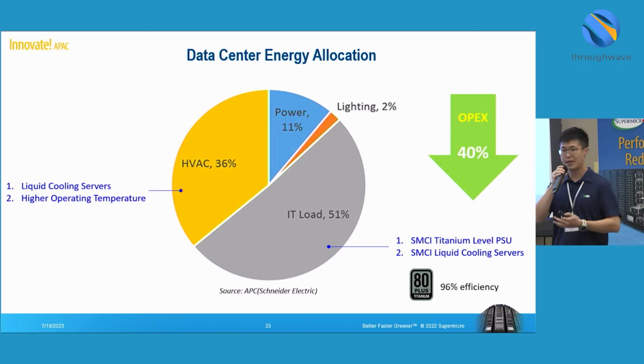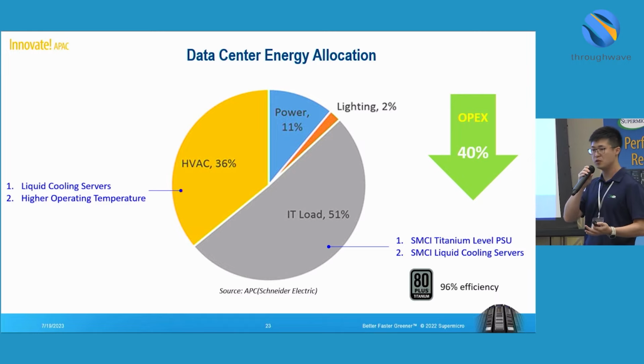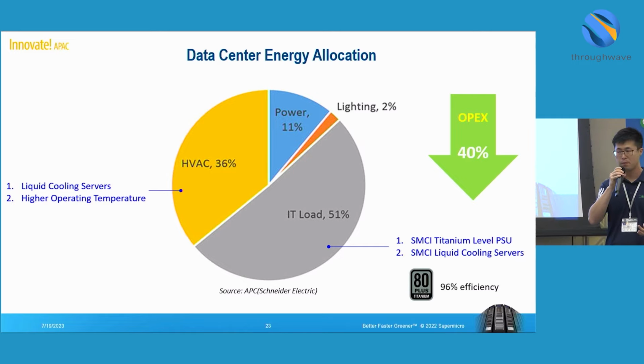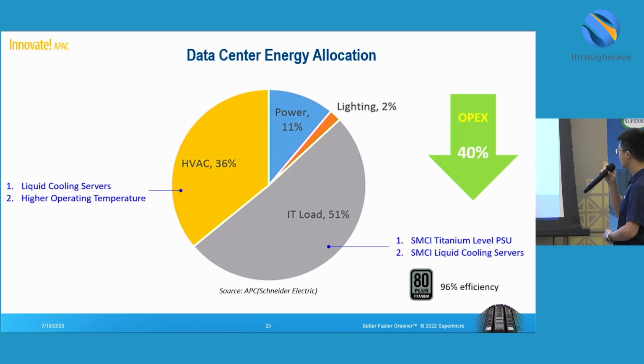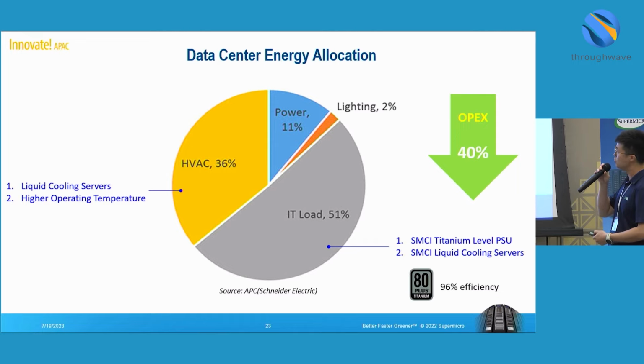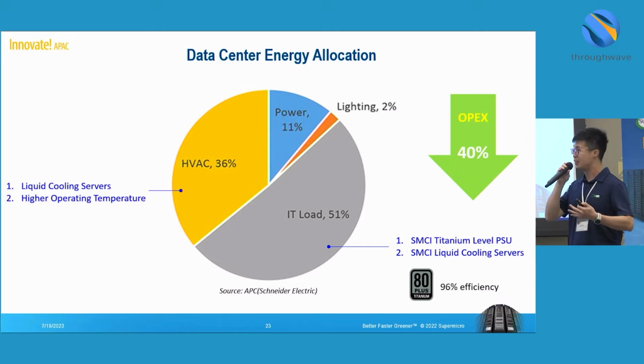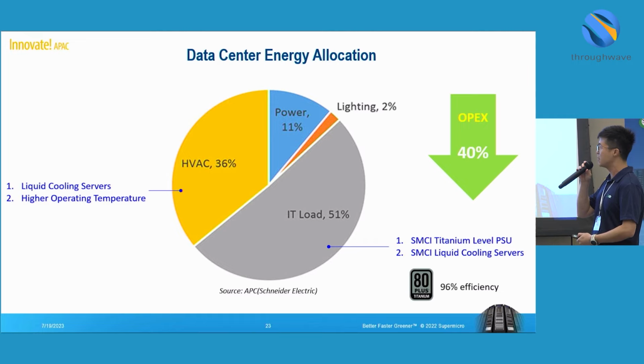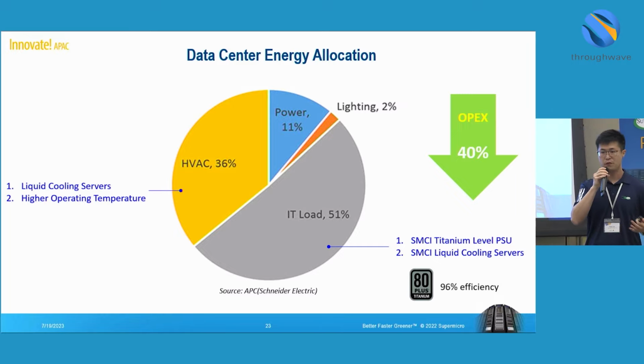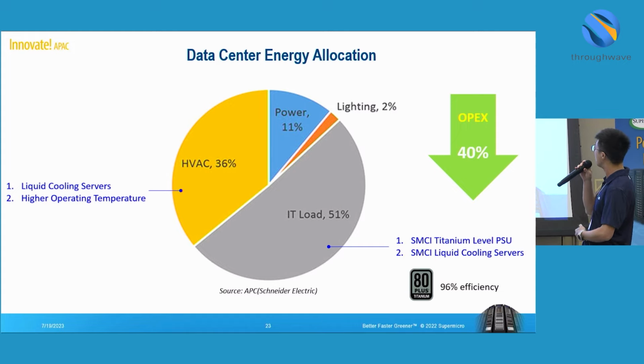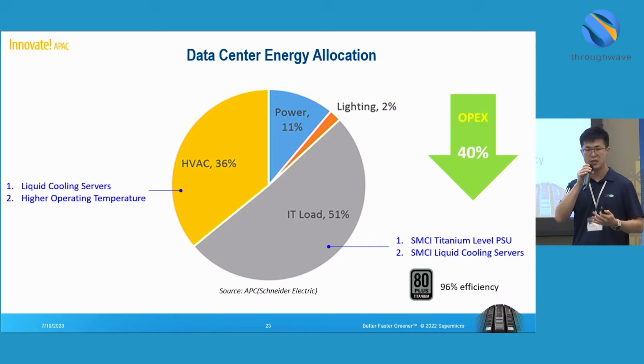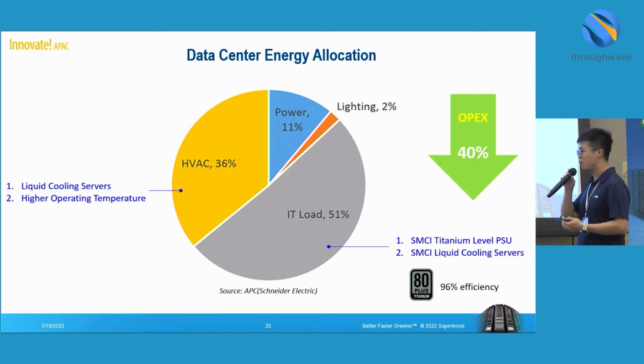For example, using titanium level power supplies, or a multi-node system because it shares the fan and power, and also implementing liquid cooling servers. As for reducing cooling power, I think the best way is to phase in liquid cooling servers, which can operate at a higher operating temperature. So basically, changing from air cooling to liquid cooling can save around 40% on operating expenses. These are the two main reasons why we need liquid cooling solutions for our servers.